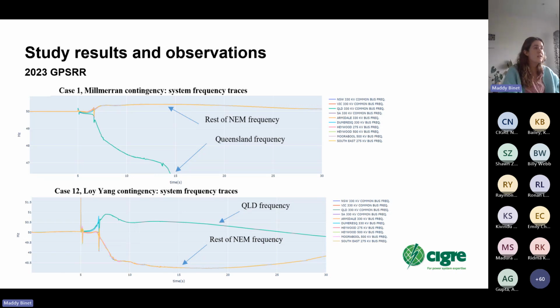Then the figure on the top shows the Queensland generation contingency event for a Queensland import condition. So we found that for 4 of the cases we looked at, there was Queensland synchronous separation following the loss of Millmerran units as well as DPV shake-off in Queensland. So we saw that the QNI flow swung up to around 1400 megawatts before tripping. And for this particular case, you can see that there was also insufficient UFLS in Queensland to prevent Queensland frequency from collapsing below 47 hertz.